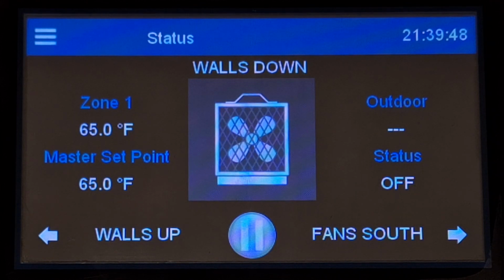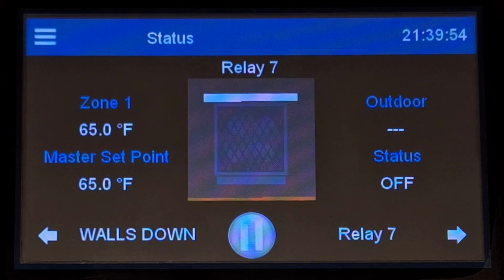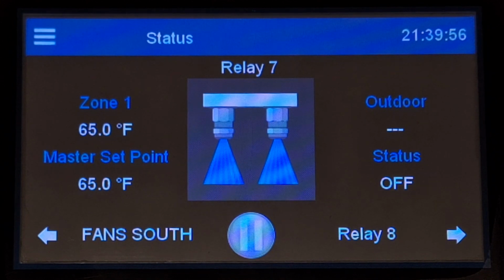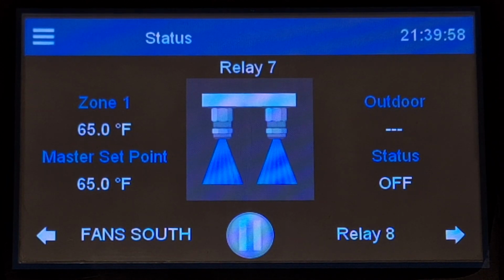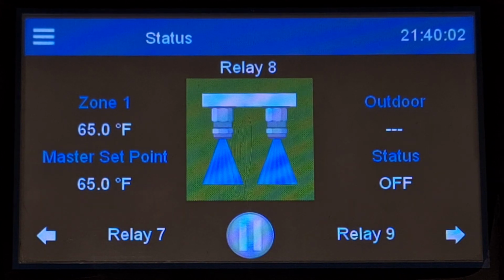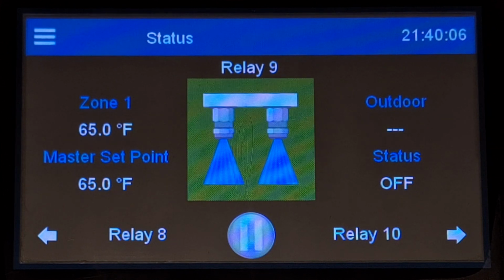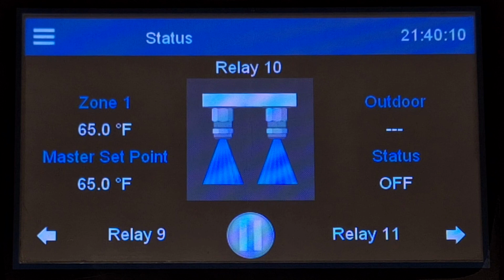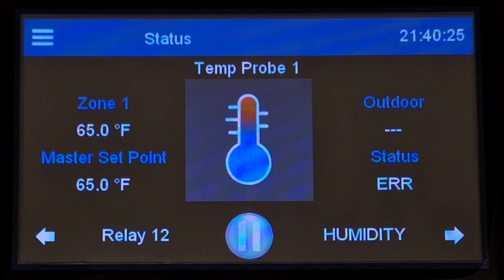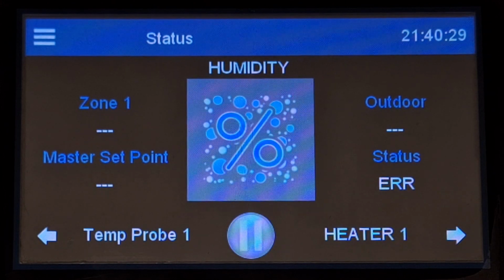It's a calculation, a formula that takes both temperature and humidity into account to come up with a value between 0 and 125. The higher the value, the higher the temperature and level of humidity. This THI group allows you to take humidity into account in a more integrated manner than just using modifiers. I will now show you how to configure a zone as a THI type.